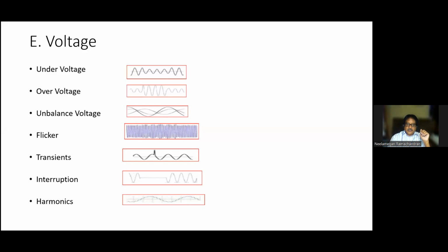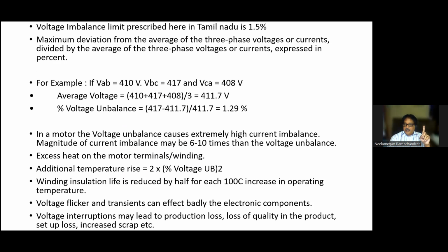This unbalanced voltage, we have a norm. Even in the EB bill, unbalance should be 1.5% across all the phases, R, Y, B. We just measure the voltage. You take the average; the maximum voltage minus the average, divided by the average, will give you the percentage. If it is more than 1.5, we can claim compensation from the service provider. That is there in the EB bill also, but we don't check and we don't claim any refund or penalty from them.